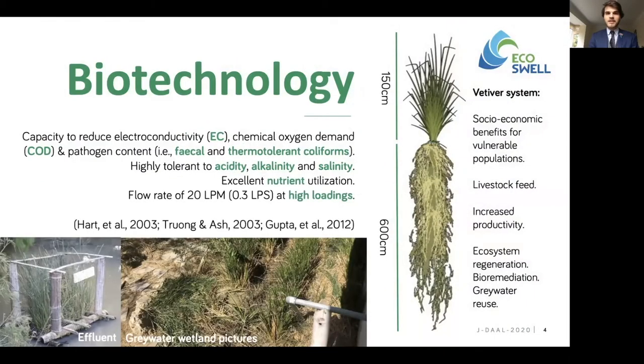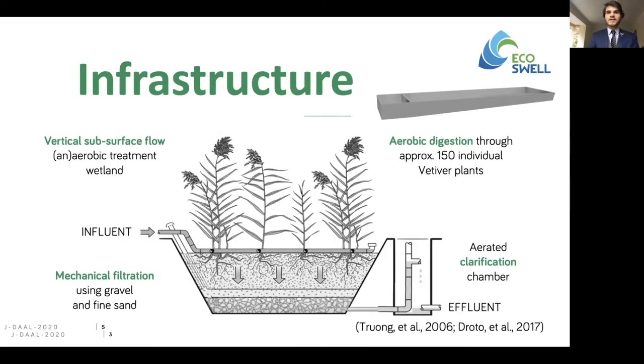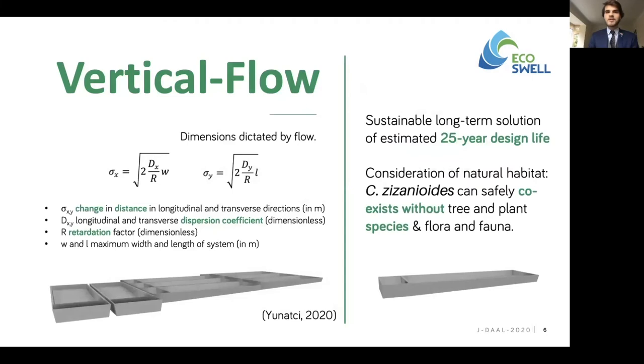We are working with Vetiver Biotechnology because of their capacity to reduce electroconductivity, COD, and pathogen content, and their ability to survive in extremely adverse circumstances. Vetiver also has excellent nutrient utilization and absorbs high amounts of carbon. Vetiver is an example of green infrastructure providing ecosystem-based adaptation services. The infrastructure includes a vertical subsurface flow wetland in which the influent is digested aerobically by approximately 150 individual vetiver plants, aerated by microbes in their rhizospheres, while simultaneously being mechanically filtered through fine sand and gravel. The wetland cells were sized according to the dispersion coefficients computed from the flow properties of the influent wastewater, the retardation factor of the soil bed, and the maximum dimensions of the system.